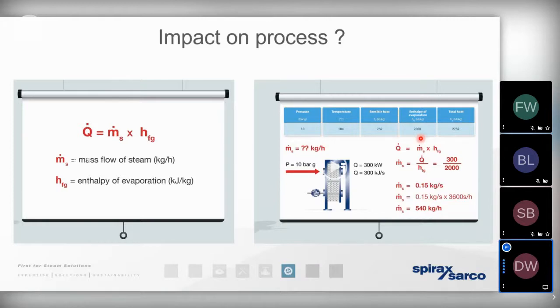So let's say that on this occasion we know the kilowatt rating of the heat exchanger. It's badged. And we need to know the mass flow rate of steam that is required to get the required heating effect. As we've mentioned, we can rearrange the equation to use what we do know to calculate what we don't know. For example, if we divide the 300 kilowatt by the 2000 latent heat energy, we get a mass flow rate of 0.15 kilograms per second, which works out at 540 kilograms per hour. So we've basically used that thermodynamic equation to calculate our steam demand and therefore to correctly size the control valve.